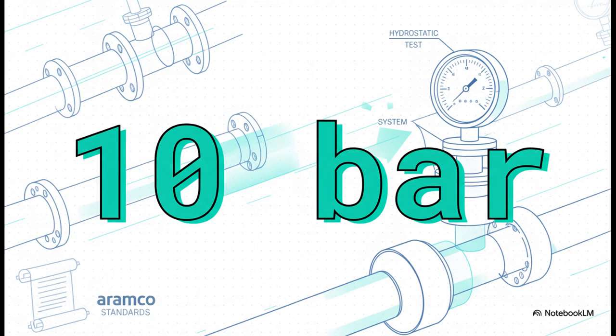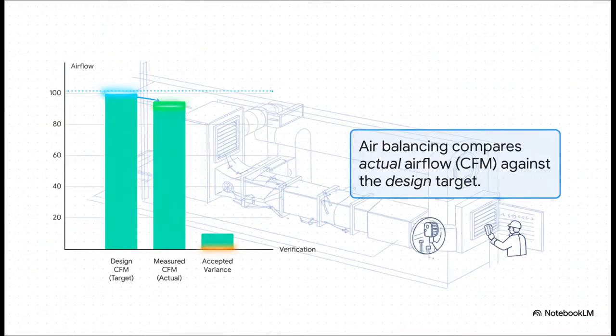And speaking of the water side, this is a huge one. Your piping systems have to go through what's called a hydrostatic test, usually at 10 bar or 1.5 times the operating pressure. This isn't just a suggestion, it's a mandatory safety check, spelled out by folks like Aramco to make sure nothing is going to leak or burst when you go live. Over on the air side, this chart pretty much says it all. The whole goal of air balancing is to measure the actual airflow coming out of every vent and make sure it matches the design. So the conference room isn't an icebox while the corner office is an oven. It's all about precision and making sure what was designed is what was delivered.